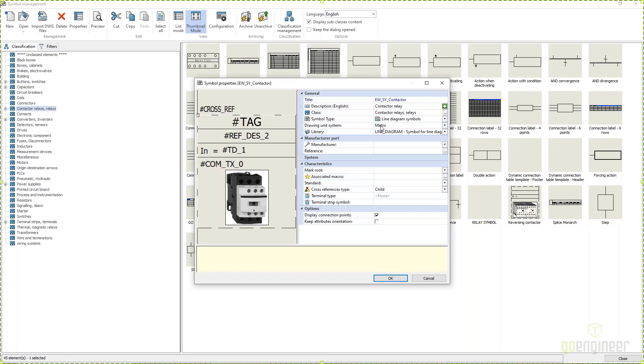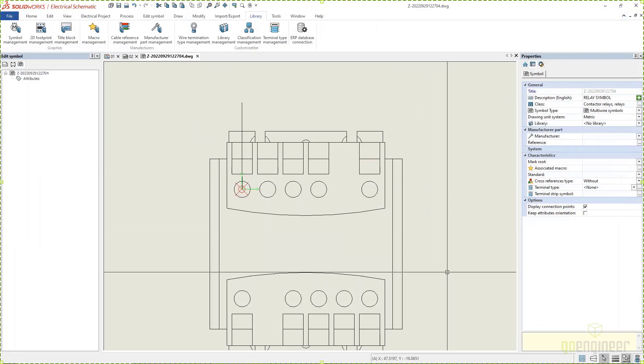When you create your symbol, you're going to specify your unit measurement. This sets up some scaling functions inside of SOLIDWORKS for the backend when we're inserting a metric symbol into an inch project or an inch symbol into a metric project. So because that setup happens as soon as you create it, best practice: don't change the drawing unit system after you've created something. If you want it to be metric, say metric. If you want it to be inches, say inches. Don't change it after the fact, because it sets up some scaling in the background and it's going to be a lot more work.